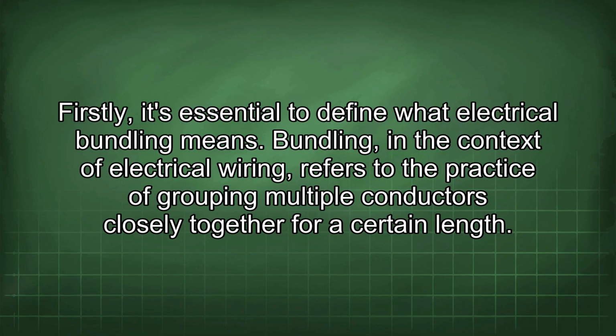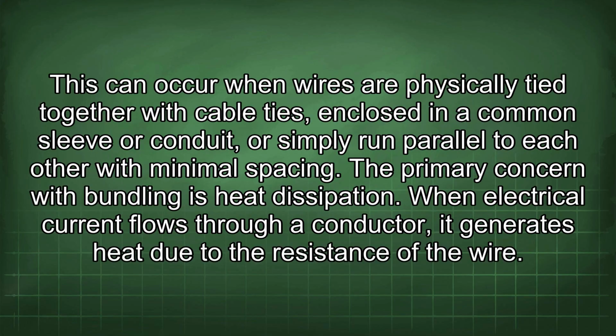Firstly, it's essential to define what electrical bundling means. Bundling, in the context of electrical wiring, refers to the practice of grouping multiple conductors closely together for a certain length. This can occur when wires are physically tied together with cable ties, enclosed in a common sleeve or conduit, or simply run parallel to each other with minimal spacing.